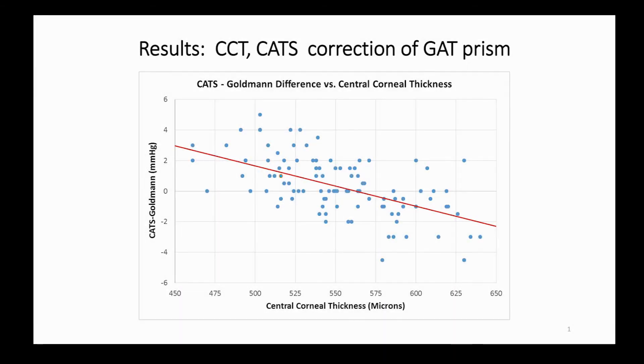We demonstrate a correction difference between the CATS and Goldmann prisms, which measures a higher CATS IOP in thin corneas and a lower CATS IOP in thick corneas, which is what would be expected. Note the IOP pressure difference is approximately zero for a nominal cornea of 550 microns. We demonstrate similar IOP difference correlations correcting for corneal rigidity and corneal curvature.